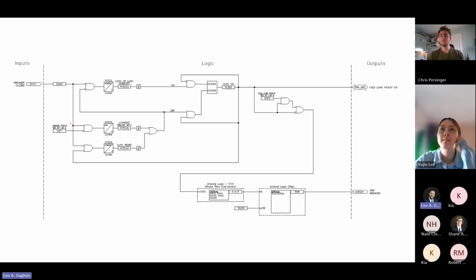Okay, so our initial condition, the breaker just opened, so we've got a 0 here, and cold load pickup is off, so we've got a 0 here. So if we've got a 0 here, we got a NOT gate right there. The breaker is open. We got a NOT gate there. That gets us to a 1. Well, where's this coming from? Okay, over here. So we got a 0 here, which means we got a 0 there and a 0 there. If both of those are zeros, this all passes through as a 0, meaning you've got a 0 and you got that NOT gate, which makes it a 1. Okay, so the breaker is open. We got a 0 right there.